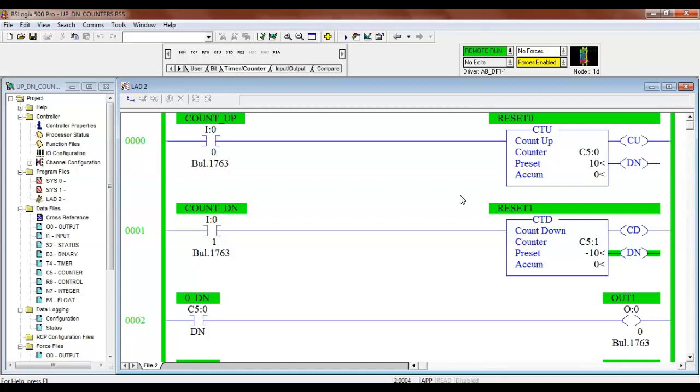So we looked at the overflow and underflow, right? If I let this counter count up to greater than 32,767, it's going to change sign. If I make this guy count less than minus 32,768, it's going to change sign. So we got an indication of that.